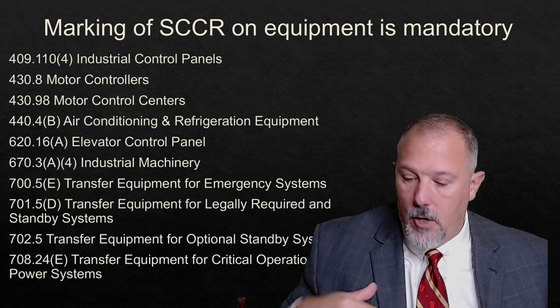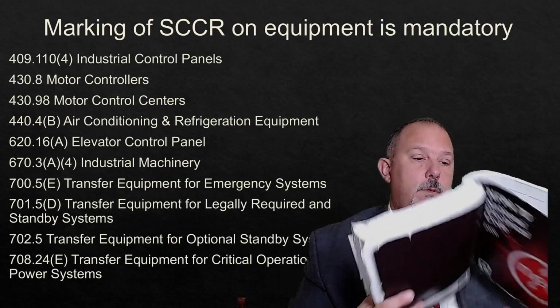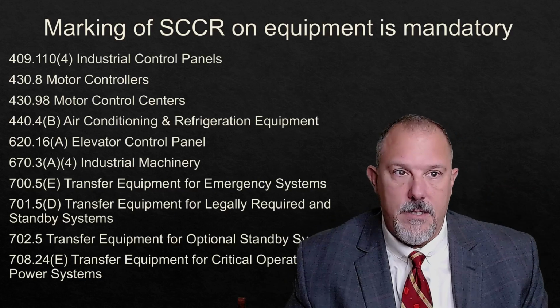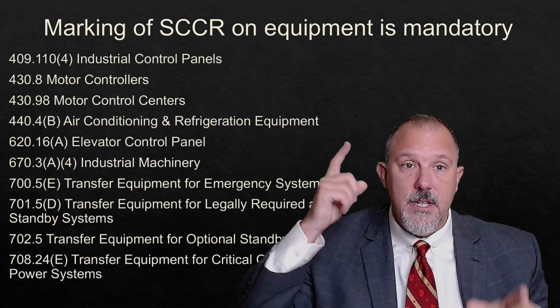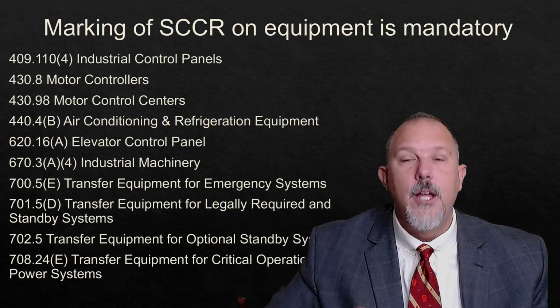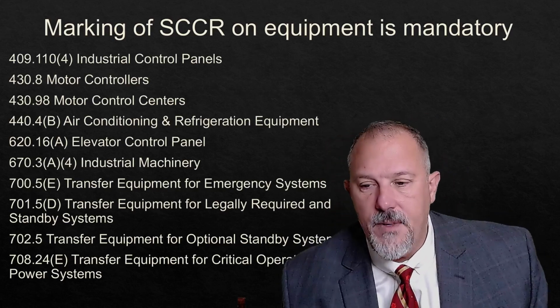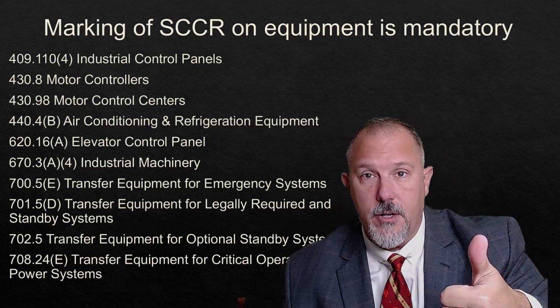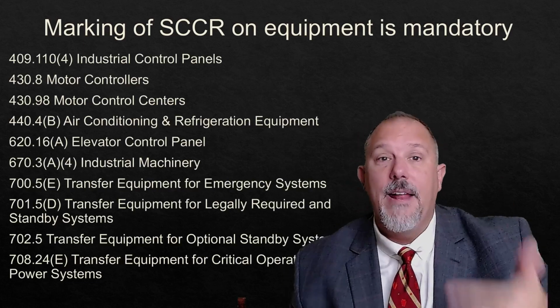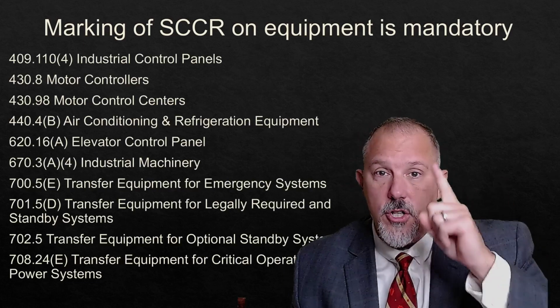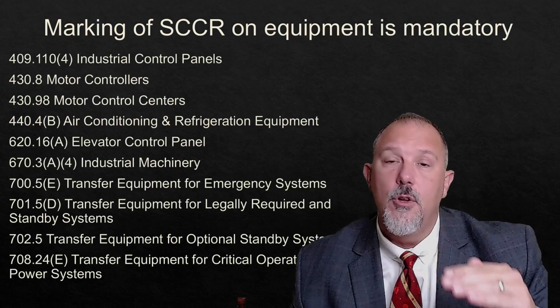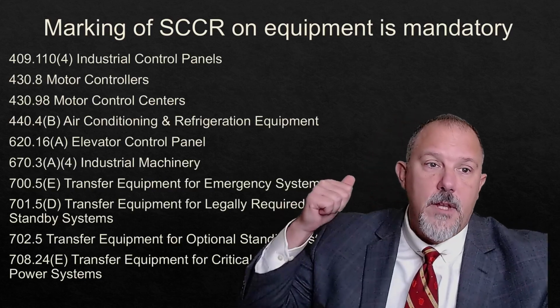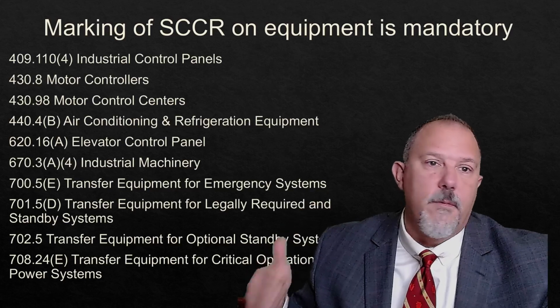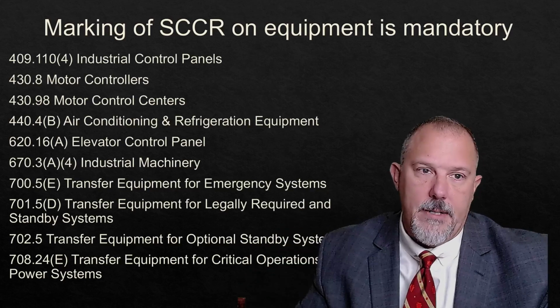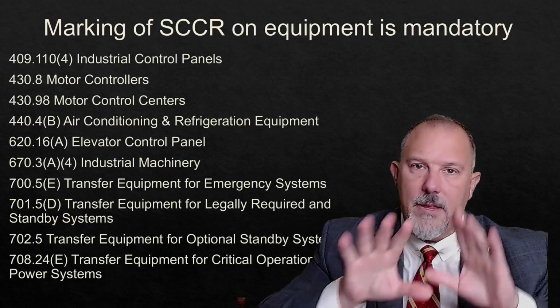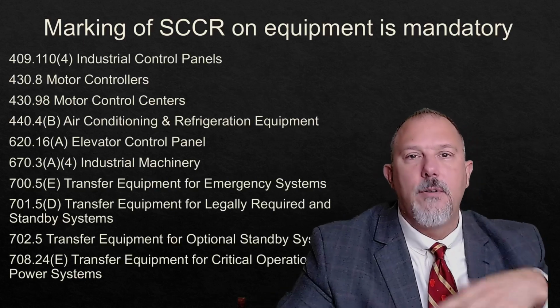All right, now in the National Electrical Code, there are many places where you have the marking of the short circuit current rating. So here's the recipe for success. First, you need to know the available fault current. Next, you need to know the rating. And next, you need to compare the two. The short circuit current rating always has to be greater than the available fault current. This is everywhere in the code where you have a marking requirement for short circuit current rating on the equipment. We're going to talk a little bit more about how equipment is rated and how it's labeled.